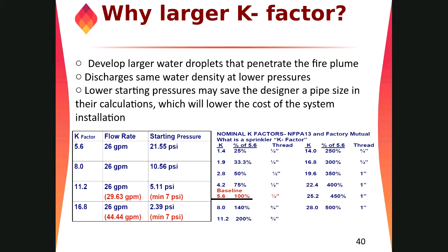So if you put the 5.6 value, it will automatically calculate how much flow and pressure is there at those points. You have to put those in the software, and also when you are making the construction drawing for the sprinkler system layout, in the drawing, also in the notes and the titles, you have to put the value of the K factor, how much flow we are getting from all those areas. So this part is only during the design of the system, and that's it, right?